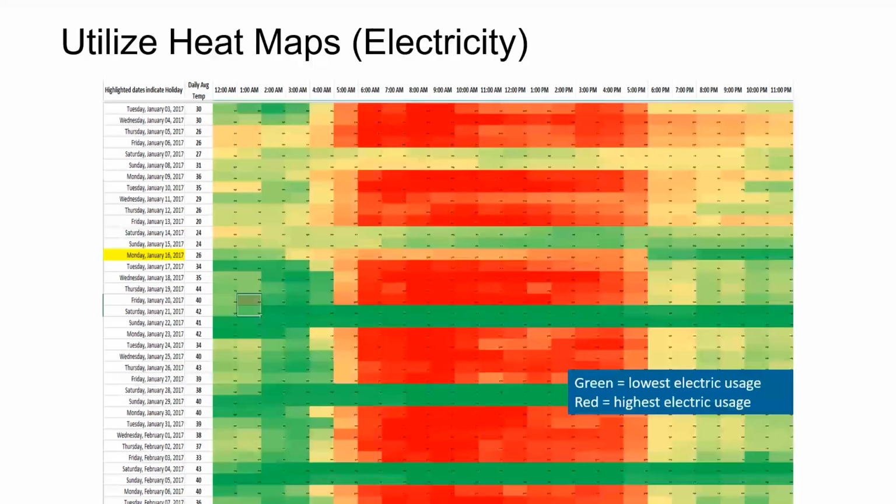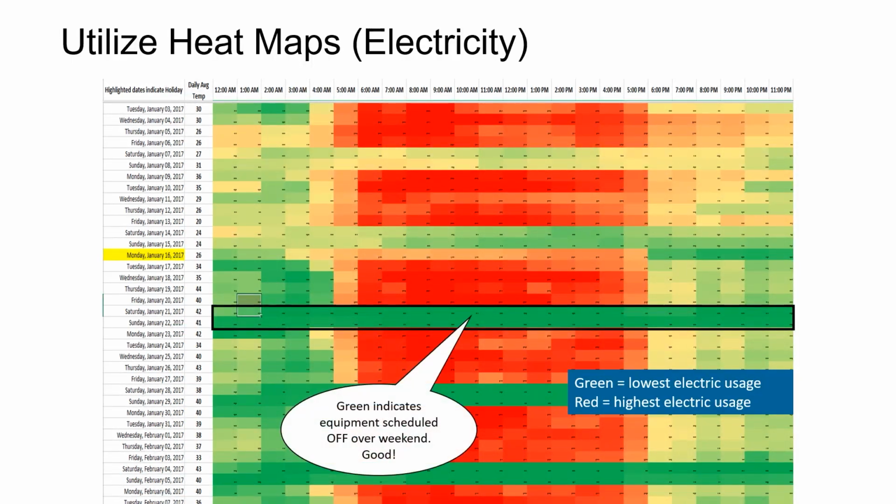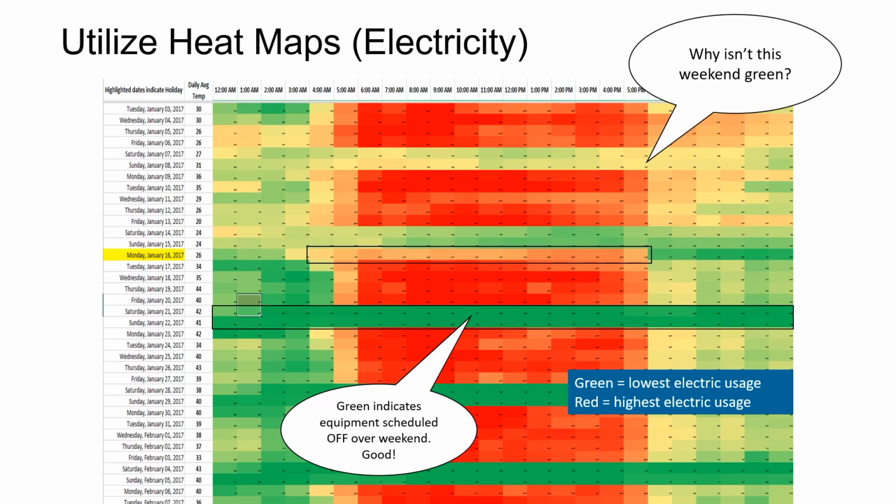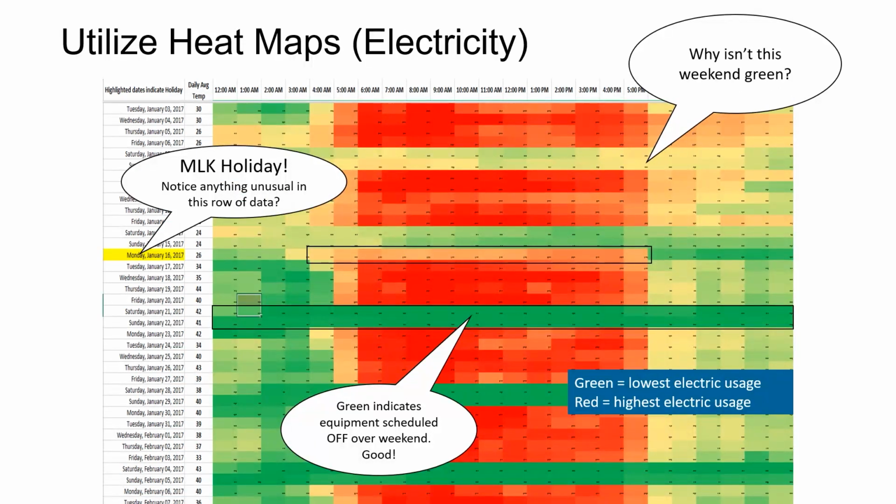Note how the operating patterns are so quickly discernible. I love that about them. You can see that evenings and weekends show up more green and yellow versus tones of red for the occupied times during the week. This example provides several patterns to investigate. How about the MLK holiday? It looks like the building wasn't scheduled off for the day. Note that the after hours operations in the first couple of weeks show more usage and slowly start reducing over the weeks. All this information is available in one snapshot, providing so much information.